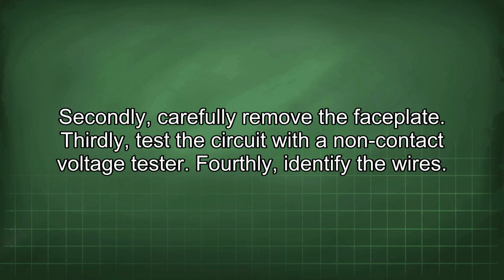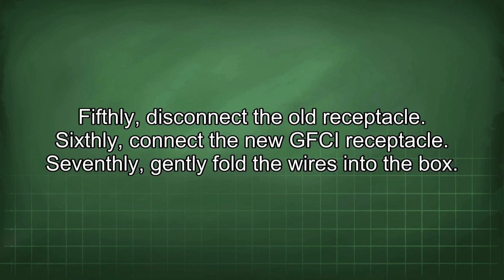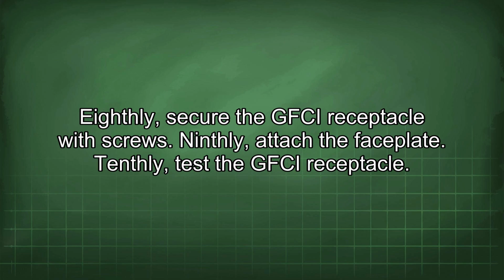Secondly, carefully remove the faceplate. Thirdly, test the circuit with the non-contact voltage tester. Fourthly, identify the wires. Fifthly, disconnect the old receptacle. Sixthly, connect the new GFCI receptacle. Seventhly, gently fold the wires into the box. Eighthly, secure the GFCI receptacle with screws. Ninthly, attach the faceplate. Tenthly, test the GFCI receptacle.